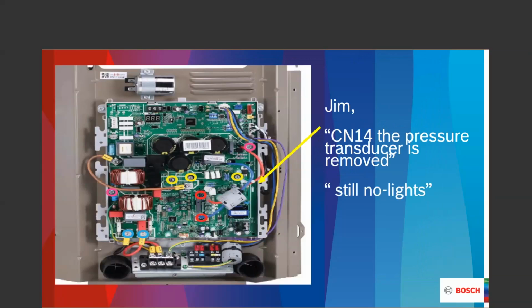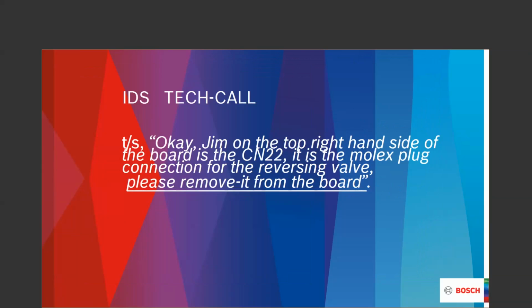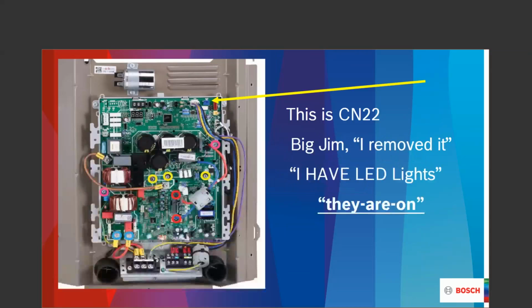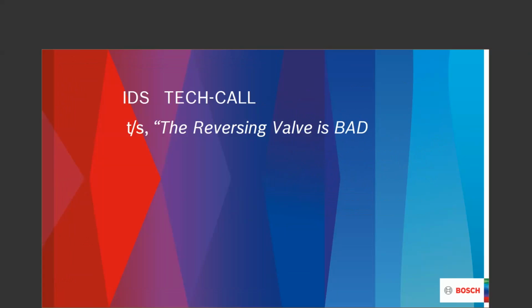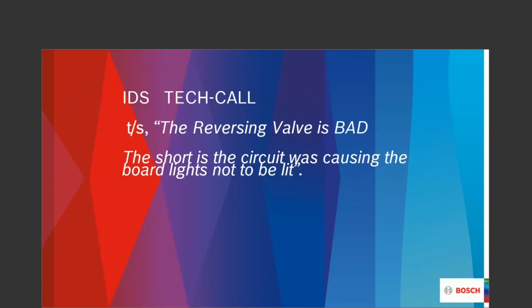Still no lights. Tech support: Okay, Jim. On the top right-hand side of the board is the CN22. It's a Molex plug connection for the reversing valve. Please remove it from the board. Big Jim says, I removed it, and I've got LED lights. They're on. Tech support: The reversing valve is bad. The short is in the circuit that was causing the board lights not to be lit.